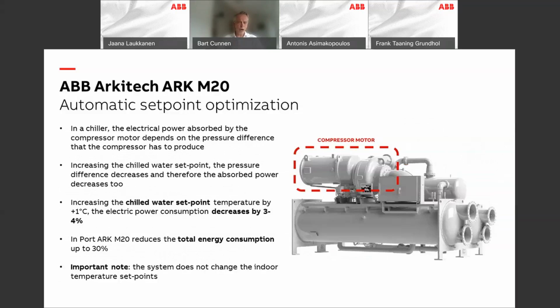One very important part of our system is that we look at the set points of the chillers. If we increase the set point by, say, 1 degree, the compressor motor uses less energy—about 3 to 4% per degree. That can add up quite a bit, and in a port situation, it can mean reducing energy consumption by up to 30%. Again, we don't change the indoor temperature.